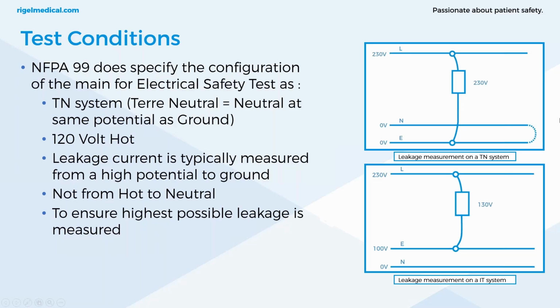The NFPA 99 does specify the configuration of the mains for electrical safety tests. So we need to be on a grounded-neutral system. This is where neutral is at the same potential as ground. It's 120 volt live. Leakage current is typically measured from a high potential to ground, and this is to ensure that the highest possible leakage is measured. On the highest potential, it says 230 here, but obviously with 120, it should be 120 to earth, or 120 to ground, with the highest potential possible.